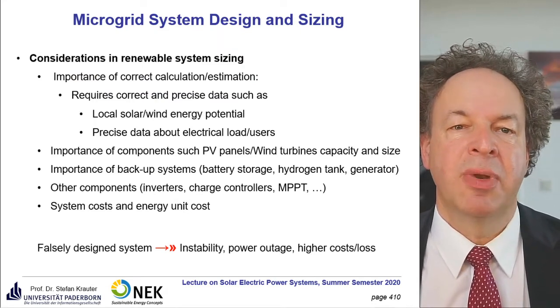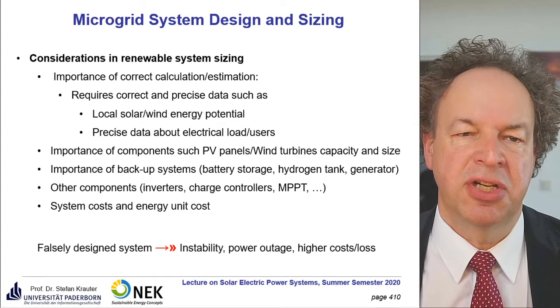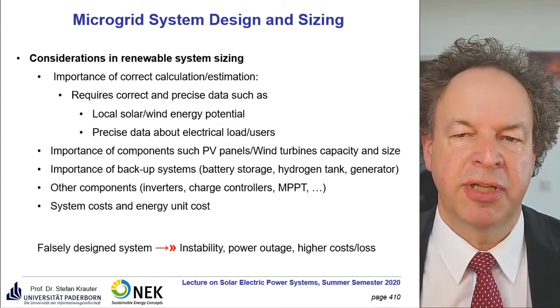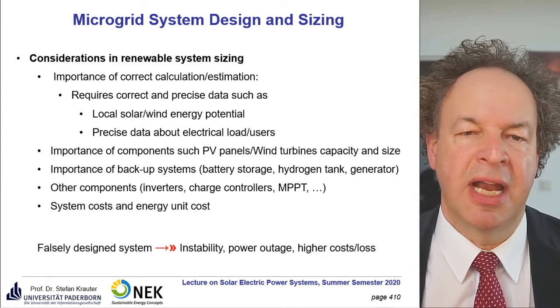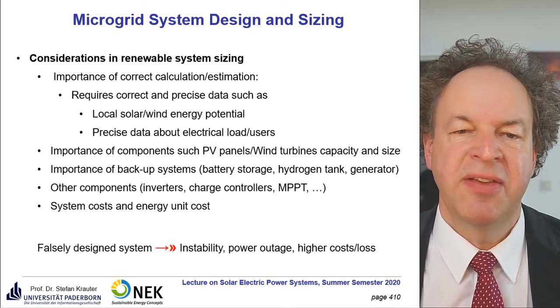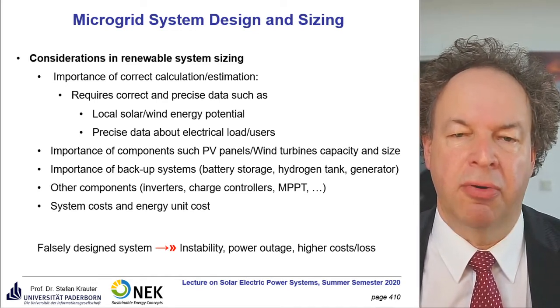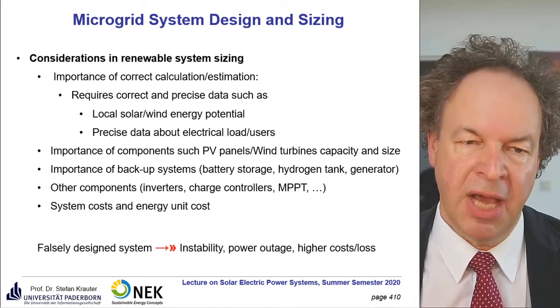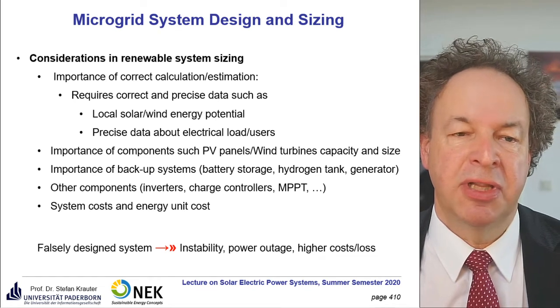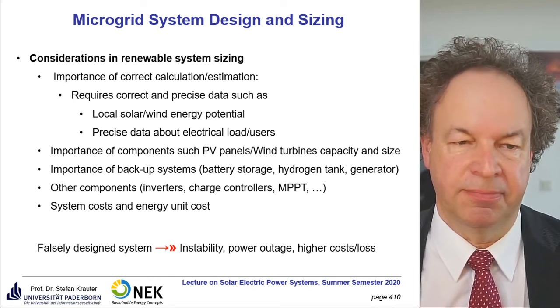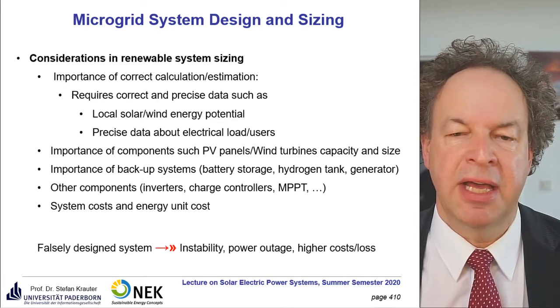Correct sizing in renewable energy systems requires precise data such as local wind and solar energy potential, precise data about the electrical load and users, the importance of components such as PV panels, wind turbines, battery storage, hydrogen tanks, generators, inverters, charge controllers, and MPPTs — maximum power point trackers — and last but not least, system costs and energy unit costs. A false system design could lead to instability, power outage, and high costs and losses.